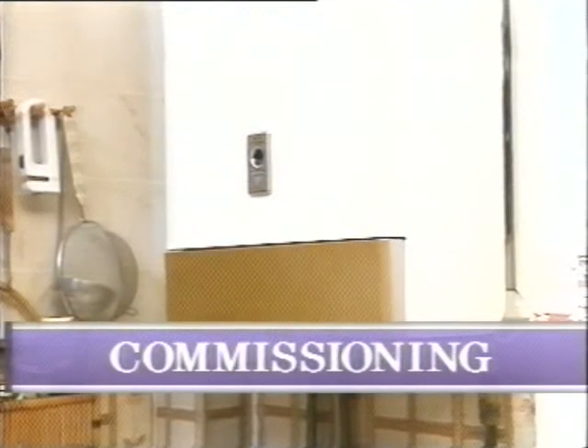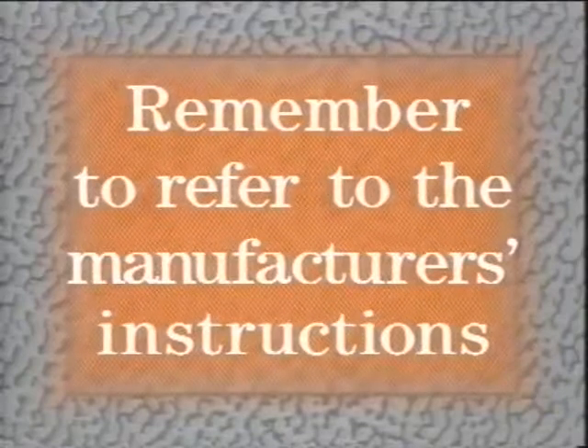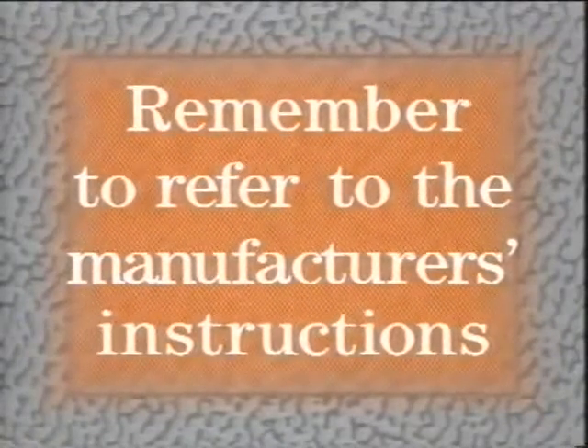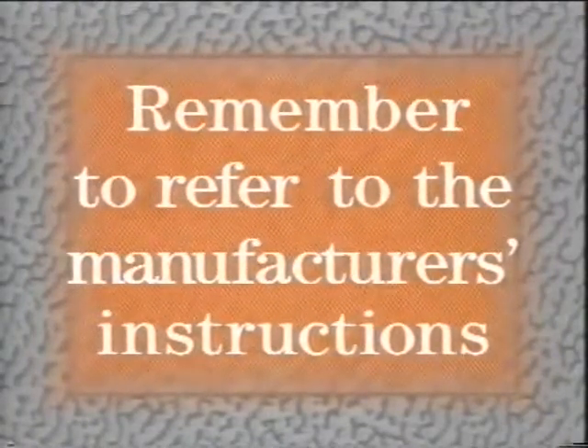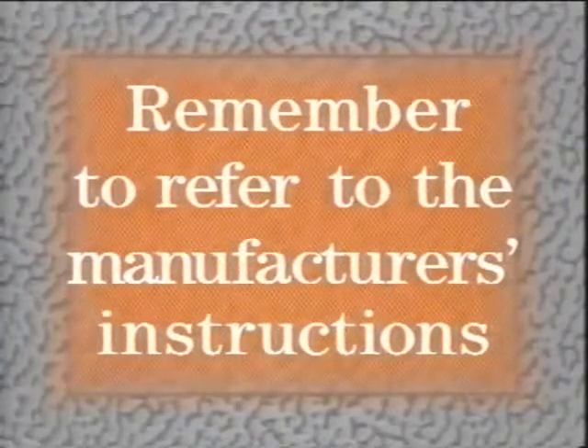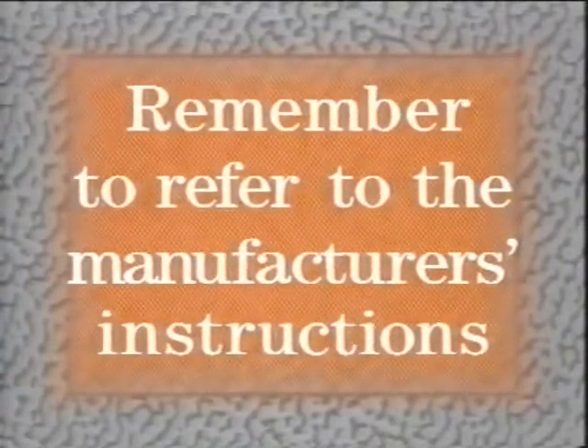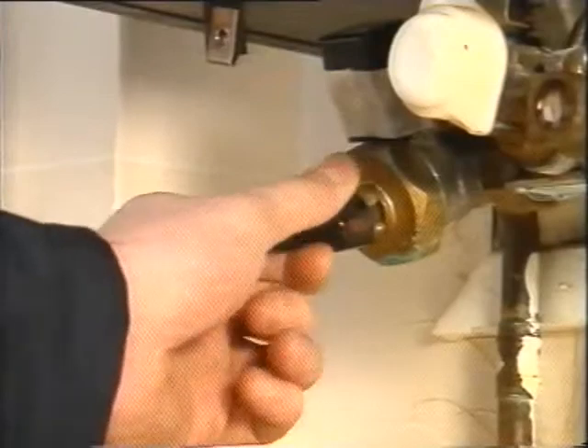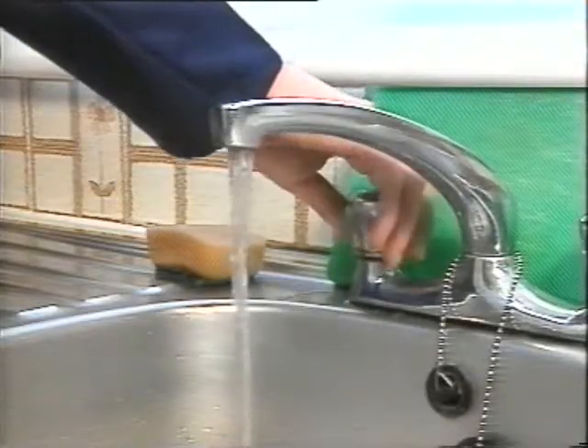Before you start on the actual commissioning of an instantaneous heater, you should first check that it's suitable for the location, that it's sound, and that there's adequate fluing and ventilation. Manufacturers spell out how to commission their appliances, but there's a basic general procedure you can use for both small and larger appliances. First, make sure the gas is off.